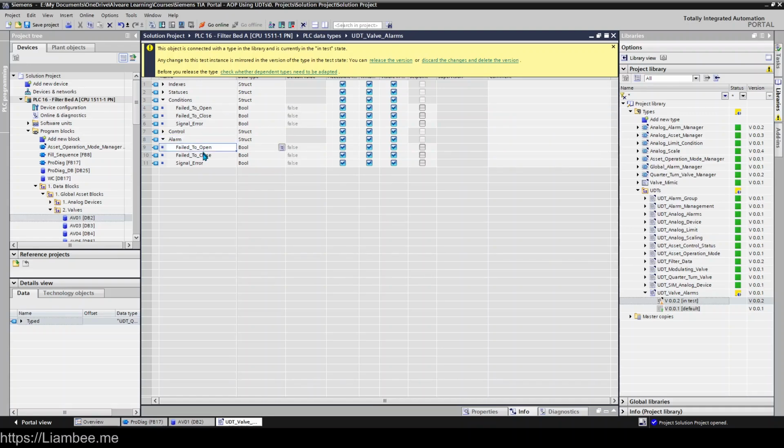We wouldn't actually have this alarm manager and be generating this alarm field. So we'd have it off the condition to say raise the alarm, because we want to raise the alarm when the condition is true. And then you use your other conditions, condition 1 and condition 2 that we looked at earlier, to control when we actually want to raise that alarm if there was additional things. Or you could just not raise this Boolean value here if you wanted to inhibit the alarm.